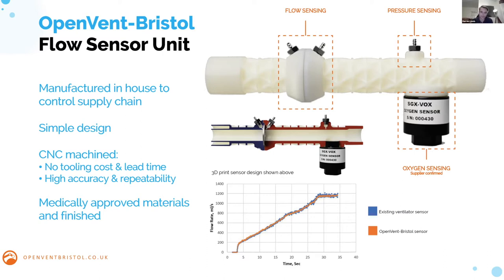What we've done is designed a flow sensor in the simplest way we could, with just a few parts, using a simple washer to create a pressure drop and measuring that. The graph at the bottom of the screen shows our sensor readings in comparison to an existing off-the-shelf ventilator sensor, and the results look pretty good.